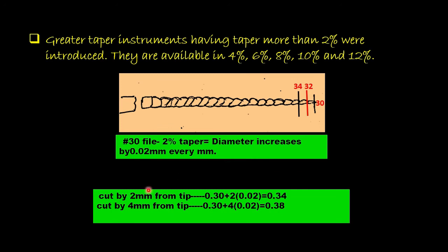Suppose if we cut the instrument 4 mm from the tip, the only change that we have to make is we will multiply 4 by 0.02 instead of 2, and this will give us 0.38. So it's simple.